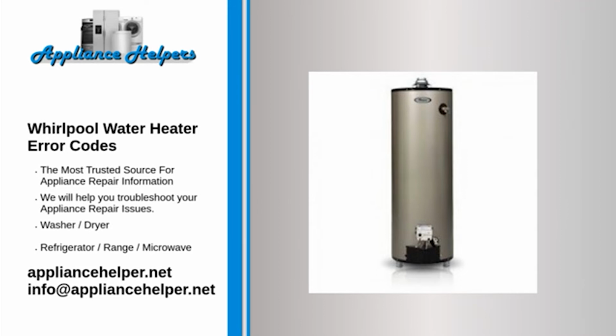Code E06. Problem: electronic thermostat failure. Fix: switch the two house circuit breakers dedicated for the water heater to off. Next, flip the breakers to on to see if the error clears. If the error does not clear, switch the circuit breakers off and replace the electronic thermostat located behind the control panel.